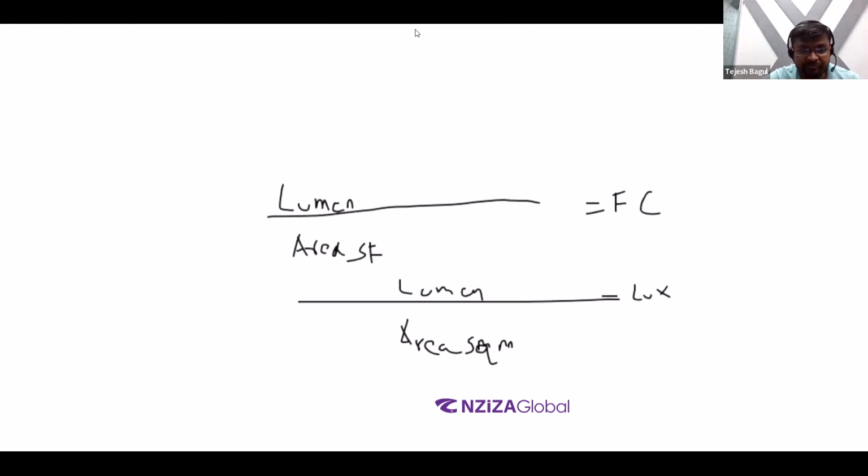That is the efficiency of the light fixtures, many times also called efficacy. What that means is when you have brand new light fixtures, you can expect the output to be the highest. When we talk about output, we are talking about the lumen. So if the manufacturer-provided lumen output is 1000 lumen, then with brand new fixtures you can expect close to 1000 lumen, maybe somewhere close by, like 995.